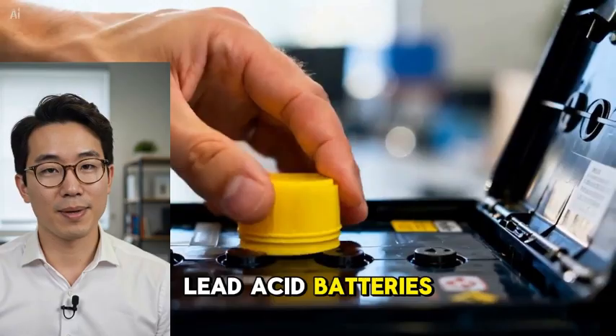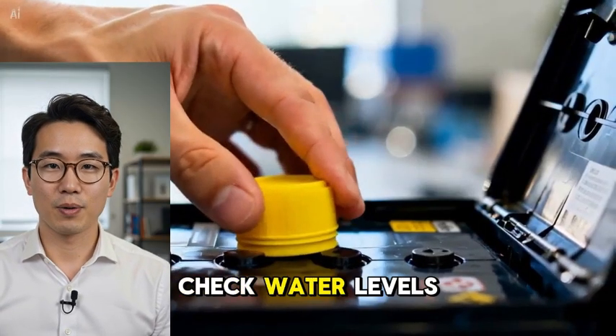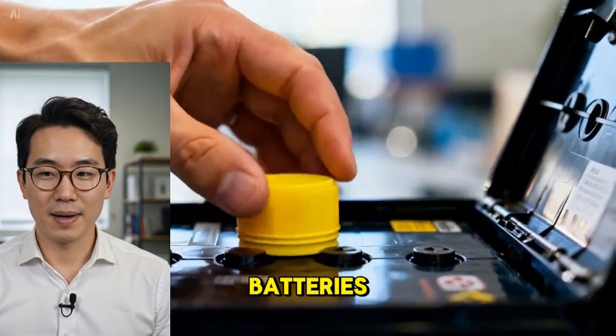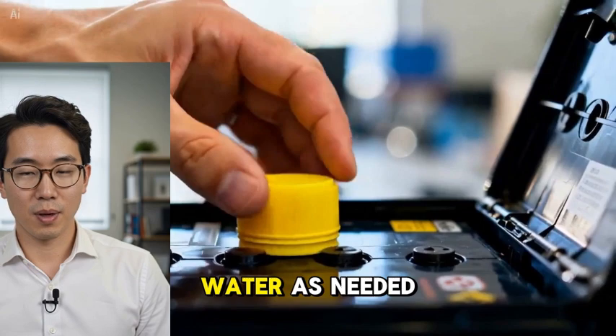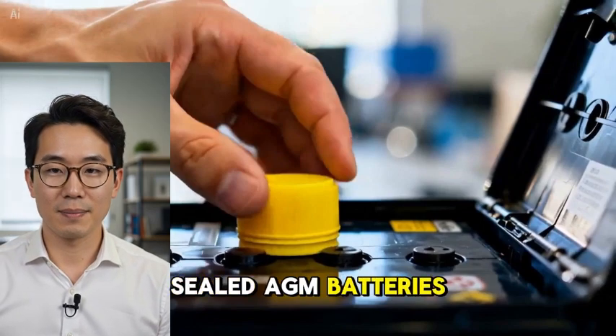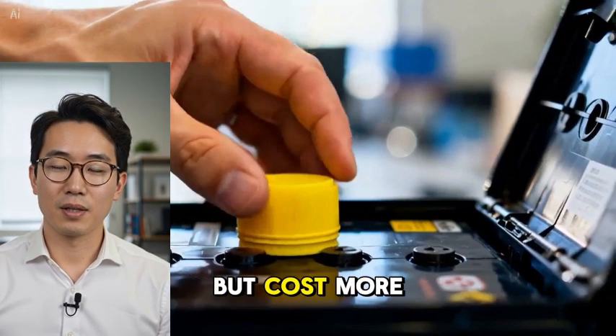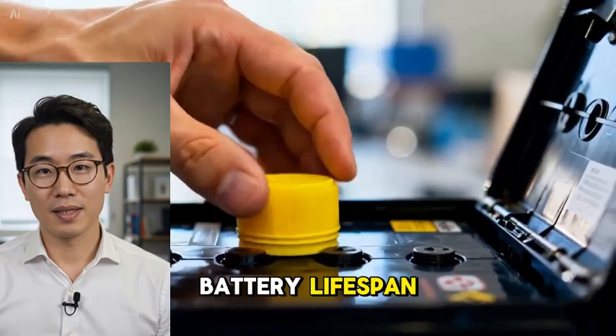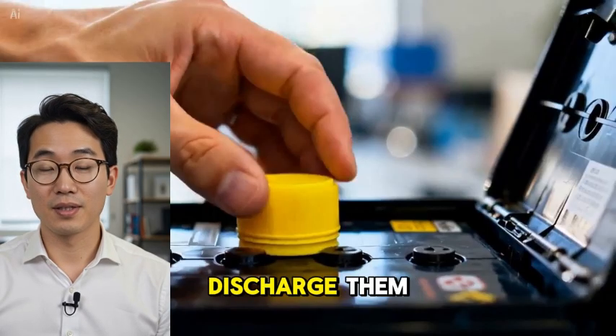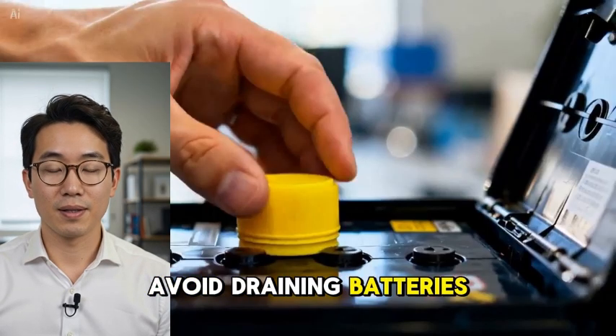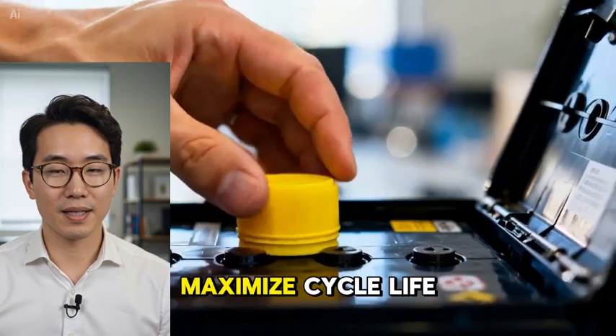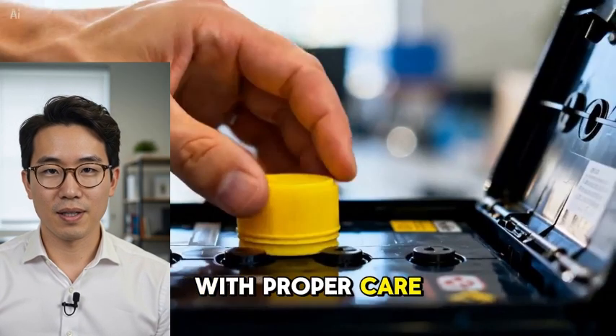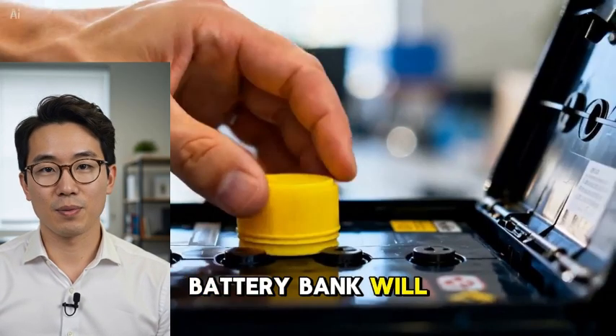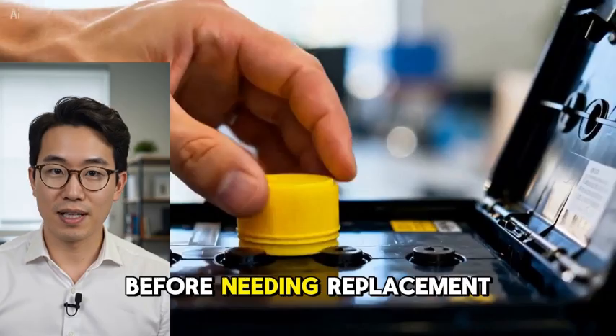Additionally, lead acid batteries require maintenance. Check water levels monthly in flooded lead acid batteries and top off with distilled water as needed. Sealed AGM batteries require no maintenance but cost more upfront. Battery lifespan depends on how deeply you discharge them. Avoid draining batteries below 50% capacity to maximize cycle life. With proper care, a lead acid battery bank will last 3 to 7 years before needing replacement.